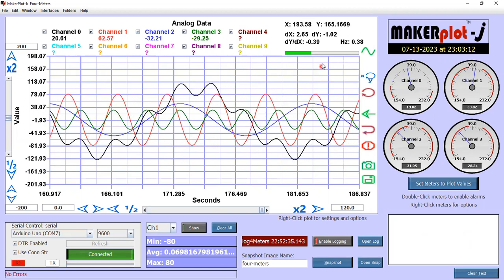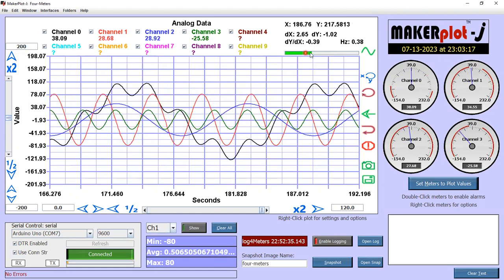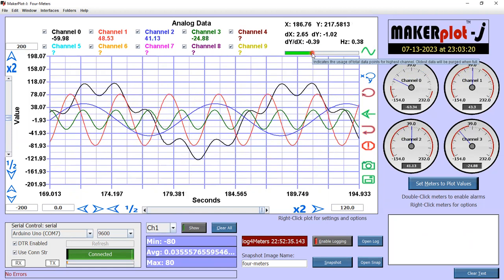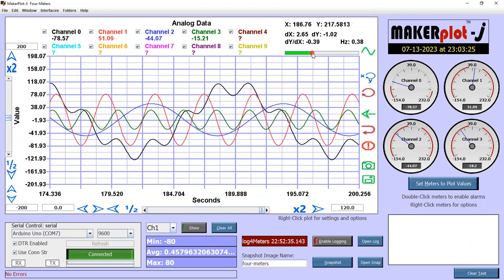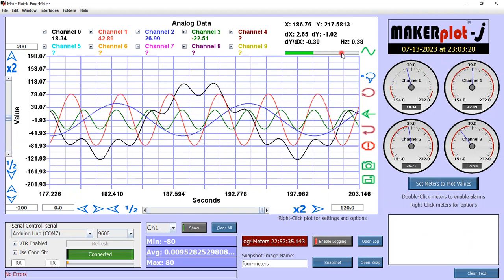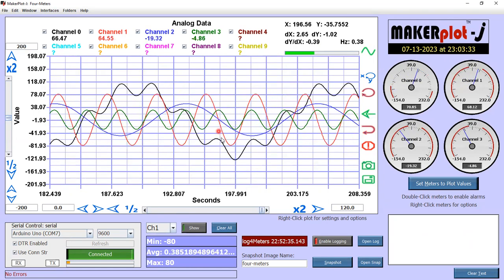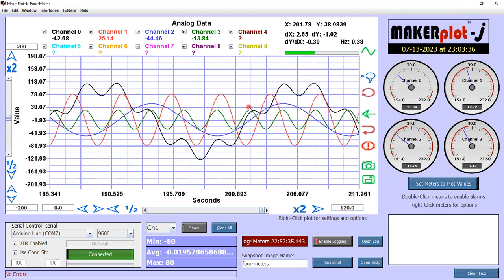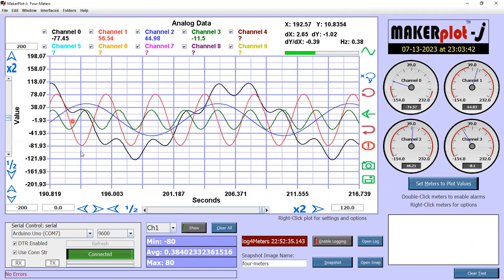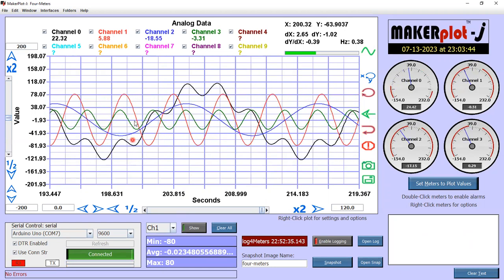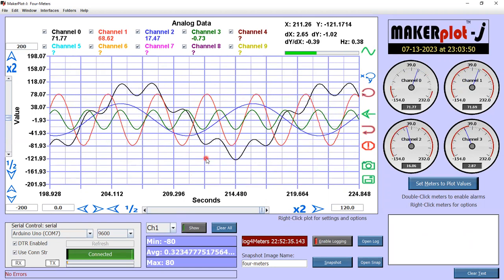Couple other things on here. One is this bar up here. Let's look at all our bars. We've got a bunch of bars around here. There's only a certain number of data points we can store in memory to keep redrawing that plot, and you just can't store forever, so there's a limit on how many data points there are. By default, I believe it's at 10,000. So it's going to start at 10,000 points for all these various traces so it can redraw from those. Now, what happens when this gets full, the oldest data will start erasing, start disappearing as it dumps out of memory. So that's an important consideration when you look at how much data you want to store.